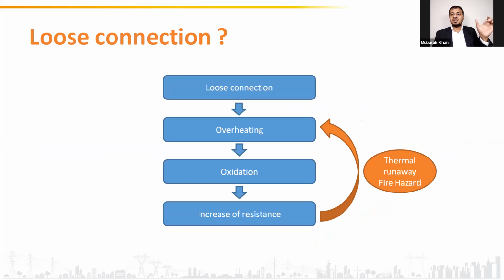So if there is a loose connection, there will be overheating. When there is overheating, it will cause oxidation at the connection. Oxidation will cause a further increase in resistance. This increase in resistance will cause more overheating. Overheating will cause more oxidation, and this cycle will keep on repeating multiple times. This scenario is known as thermal runaway, a fire hazard in electrical panels or electrical joints. This can cause the busbar or the cable to heat up to such an extent that your PVC insulation may start to burn, or if it heats further, it may cause the aluminum or copper busbar conductors to melt.